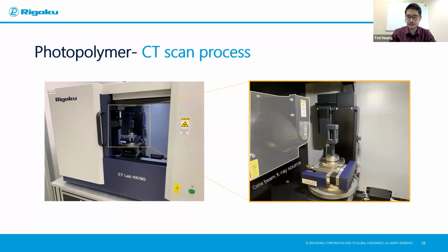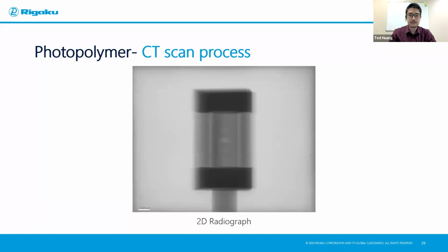And on the left, this is the cone beam X-ray source. When the X-ray turns on, this is roughly how the X-ray shines, where we get our image. And this one, we have actually quite a good voxel resolution. Despite being a small profile benchtop, you have a highest voxel resolution of 2.1 micron. When you turn on the X-ray, what the detector sees is like this.